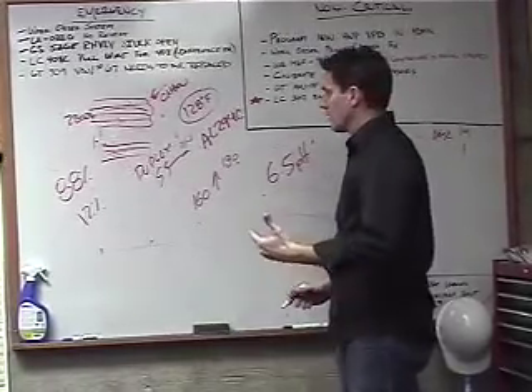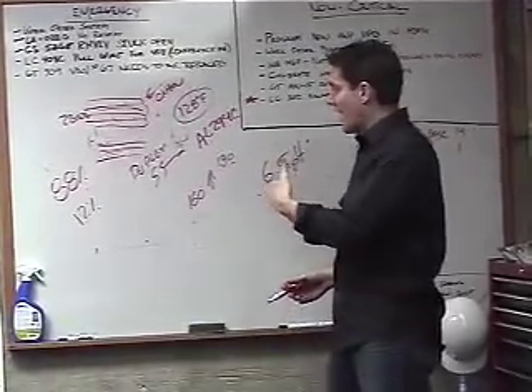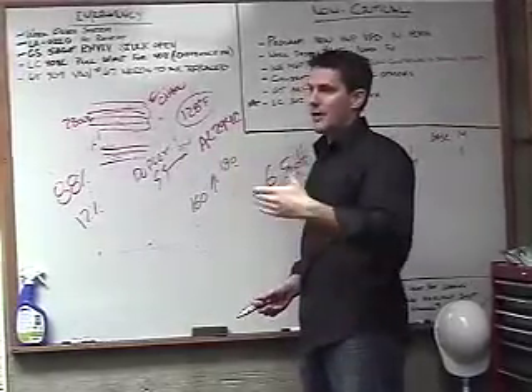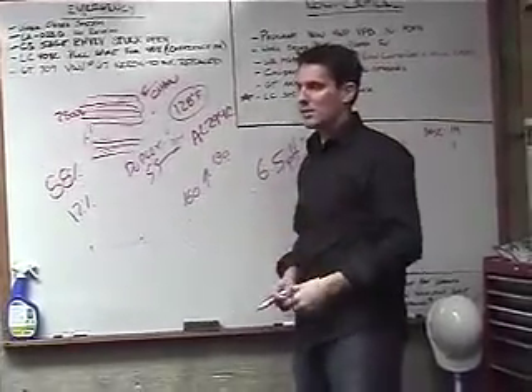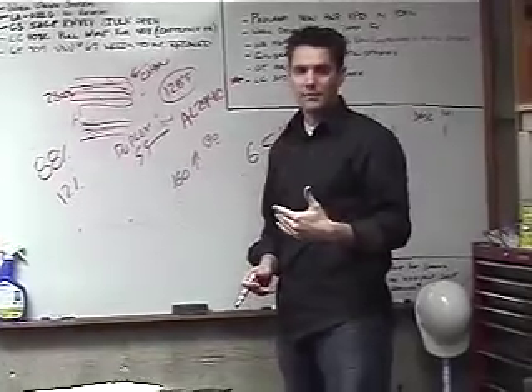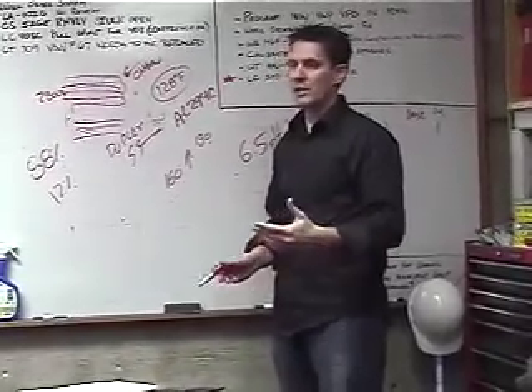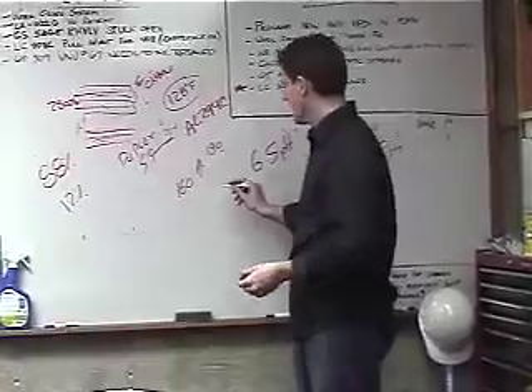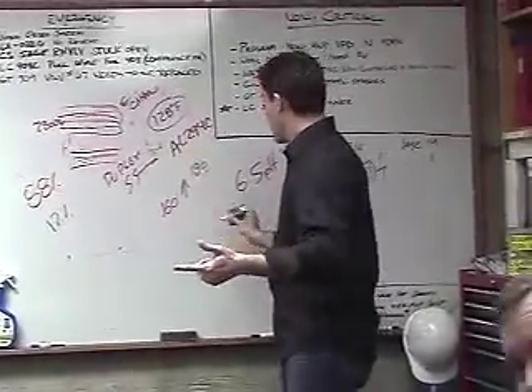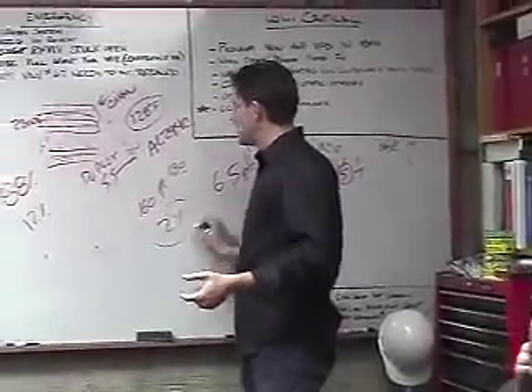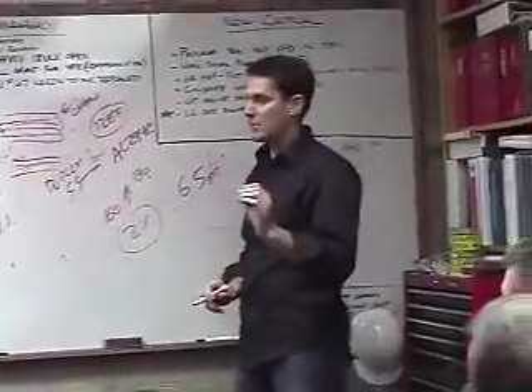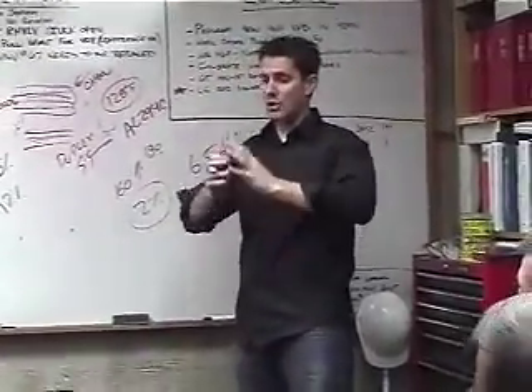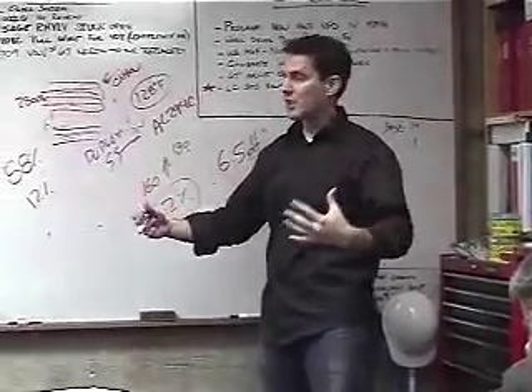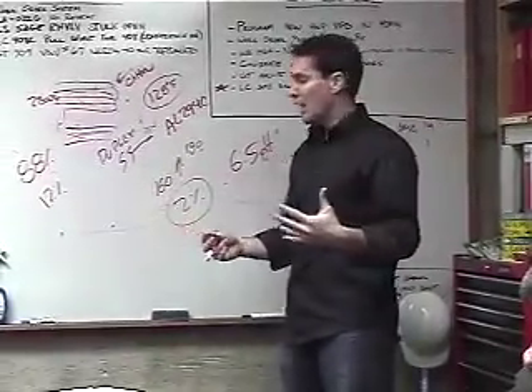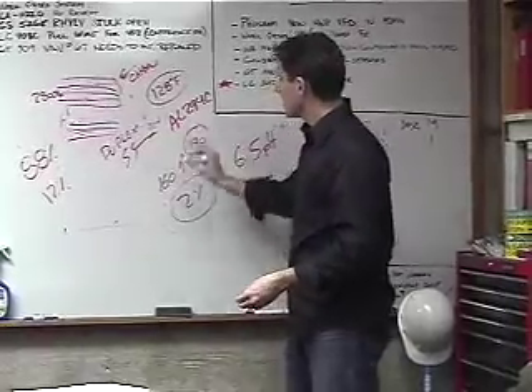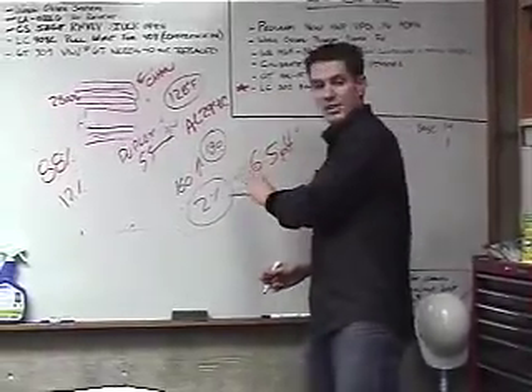I don't know your system well enough, but any system we can make do this. Your heating system was designed for the coldest day of the year. How often does that occur, percentage-wise? Not this year, it's not going to happen, right? On an average, you might get it 2% of the year. You'll be at the coldest temperature outside, and then you're going to have all of your control valves open 100%. You're going to be putting as much heat in the building as you can. And maybe they sized your building for 180 degrees supply temperature on that coldest day of the year.